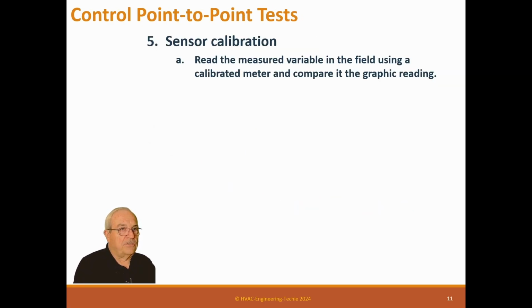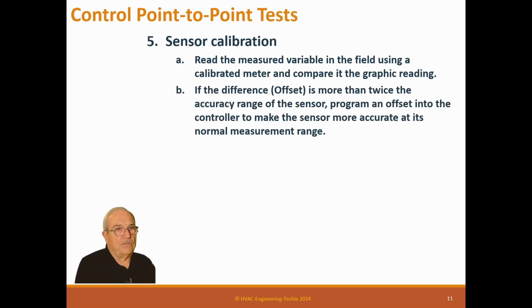Sensor calibration again: read the measured variable in the field using a calibrated meter and compare it to the graphic reading. If the difference, the offset, is more than twice the accuracy range of the sensor, program an offset into the controller to make the sensor more accurate at its normal measurement range. So we're trying to get this. In other words, if you have a wall sensor that goes from 55 to 85, that's its range. Well, you want it working really good at 75. You want it to be very high accuracy at 75. You want 75.1, 74.9, something like that would be really great.